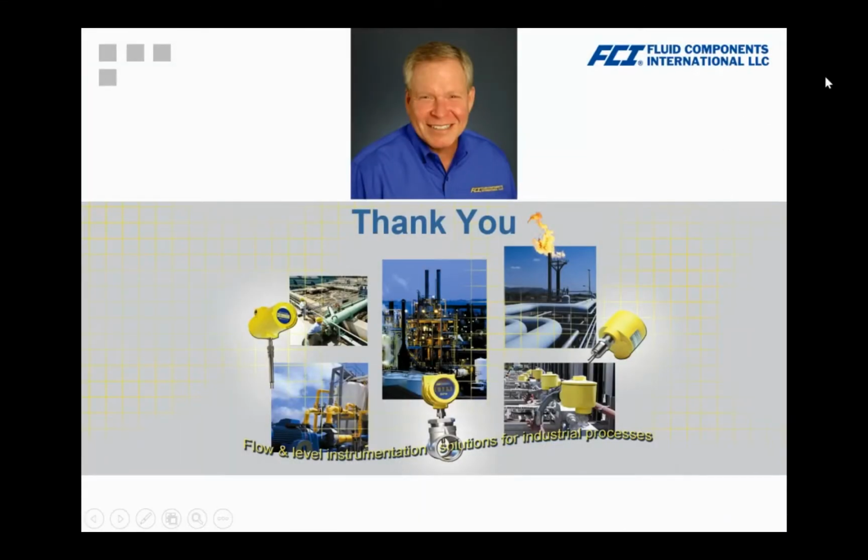Let's see what else we got. What is the increase in pressure drop due to the flow conditioners? Very good question. Of course, it depends on the velocity of the flow and the pipe diameter. But typically, we're talking about anywhere between 2 to 10 inches of water column. So it's relatively low. But it is a problem in such cases where you've got flare gas or extremely low flows. You have to be very careful with the pressure drop. But typically, it's between 2 to 10 inches of water.